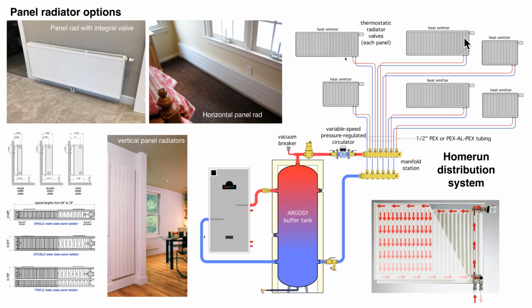So over here on the right, this is called a home run distribution system. It's a very simple idea. We're coming out of our buffer tank. We've got a variable speed circulator. We go to a manifold, and each radiator gets 1/2-inch PEX, or if you prefer, PEX aluminum, PEX tubing. So each radiator is on its own parallel circuit, all sourced off the same manifold station.